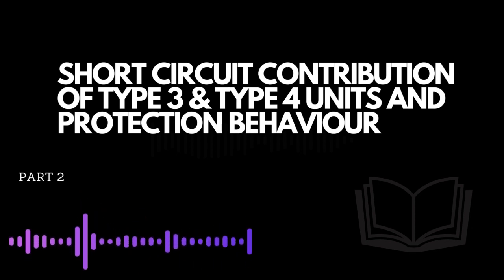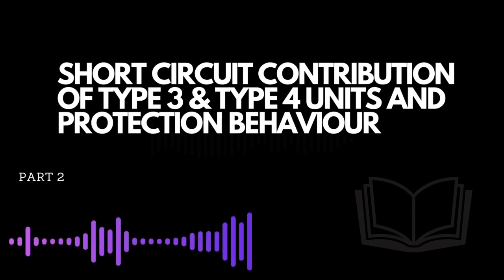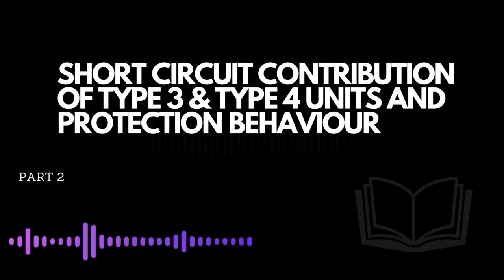Injection of negative sequence strategy. In this case, the performance of algorithms based on the phasor angle difference between negative sequence current and zero sequence current is expected to work properly under unbalanced faults. As this function is a two-ended protection or single object-oriented protection, short-circuit currents under fault condition could be enough to pick up the function, regardless of the kind of generation connected to the end buses. It could be guessed that as long as you have a strong end with synchronous generation, the pickup level will be asserted for the weak end too.